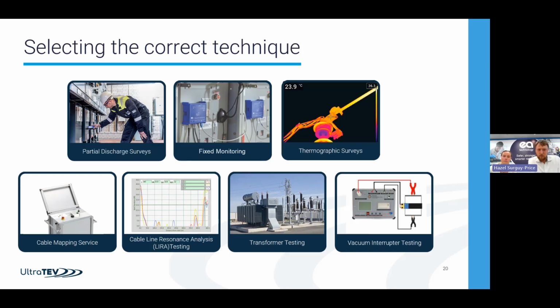Some other techniques you could choose to use are more offline services. So the cable comes out of service, the switchgear comes out of service for these activities. And whether that be the cable mapping side of things, so this is where you apply a lower frequency sine wave to the cable. That allows you to again look for PD, for breakdown of the insulation, and give you a distance down the cable. It has the advantage over doing it online that there's less noise typically.